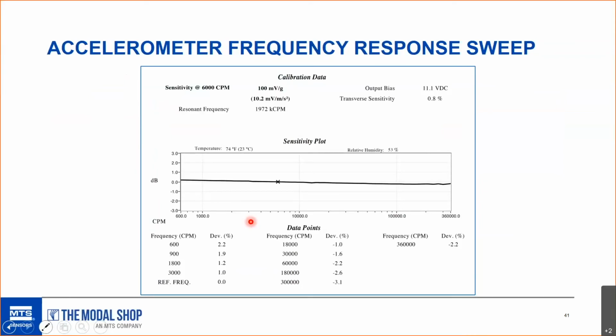But the main takeaway from this graph is that we're confirming the accuracy of the accelerometer throughout the frequency range. Accelerometers are used to pick up vibration at 1 and 2 times running speed, as well as gear mesh and inner and outer race bearing fault frequencies. So it's important that we test the full range of the transducer to ensure accuracy for all of those faults. No matter what type of faults the machine is producing or what you're looking for, you know that you're getting an accurate signal from the accelerometer.